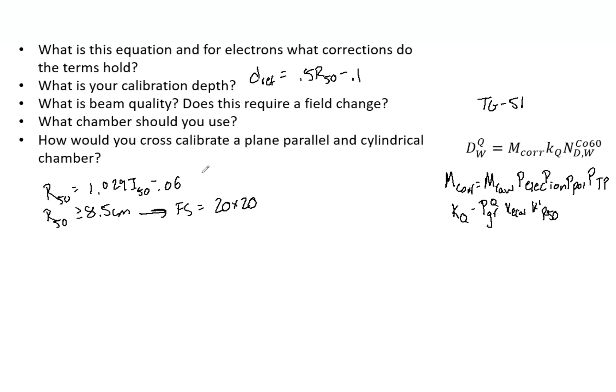How would you cross-calibrate a plane parallel and a cylindrical chamber? First thing is you want to use the highest electron energy possible. Ultimately, you're trying to find KE-cal and the absorbed dose-to-water calibration factor for a plane parallel. That's ultimately what we're trying to do. Second step is to find the K-prime R-50 for a plane parallel chamber using the R-50.